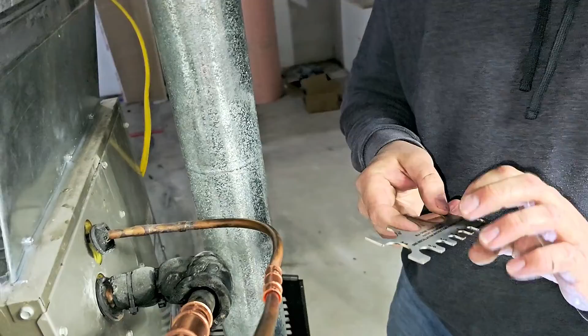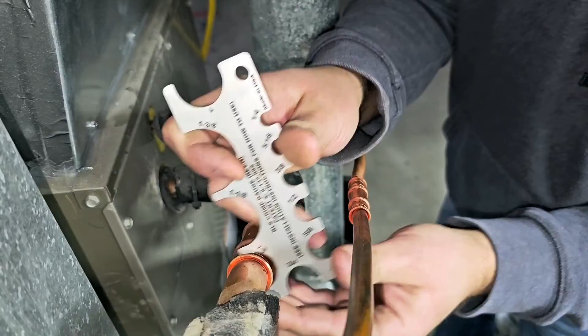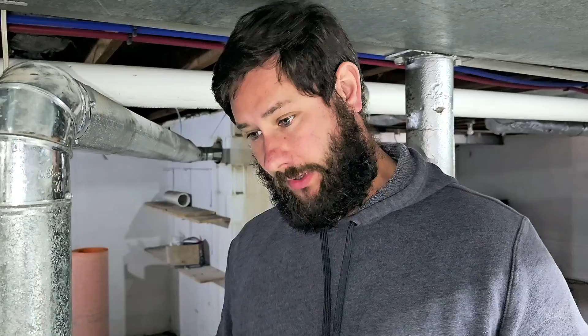Now to make sure that we got a good crimp, our crimp gauge. All right. So 7/8, 7/8, 7/8, 7/8, 3/8, 3/8, 3/8, 3/8. You should be able to see RLS, which we see it. Now we're going to do a nitrogen pressure test, put some soap bubbles on these connections here, and then we're going to do a vacuum process. So then we're going to put it all back together and fire it up.